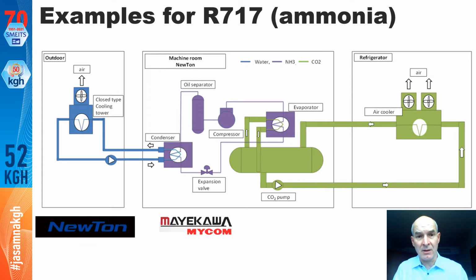This is another example of a charge reduction system. You can see that the ammonia part is in the middle of the unit, while CO2 is used to circulate it through the different evaporators, absorbing the heat, which is then recondensed in the evaporator of the ammonia system. By doing so, you can separate ammonia and food products and have high safety in your production plant. Even the outdoor unit has a kind of secondary loop, so the amount of ammonia is rather limited, and still this is a very energy efficient system.